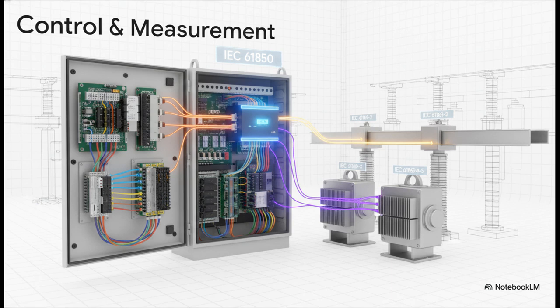But it's not just about raw power. It's also about intelligence and control. This here is the substation's nervous system. We have standards for the current and voltage transformers. Those are the senses of the substation. And for its brain, the substation automation system, or SAS. And that whole control network is governed by a real game changer, the IEC 61850 standard. We'll be talking more about that one in just a bit.